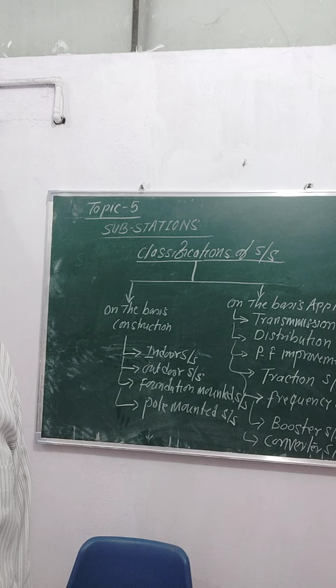Now it is increased to 500 kVA, and voltage we select either 11 by 0.4 kV or 33 by 0.4 kV, depending upon the input line available and power demand also, because 33 kV will naturally carry more power compared to 11 kV. So I will take the pole mounted substation estimate. Next time I will first draw the diagram, then write down the list of material, and according to that diagram you can prepare the estimate easily.